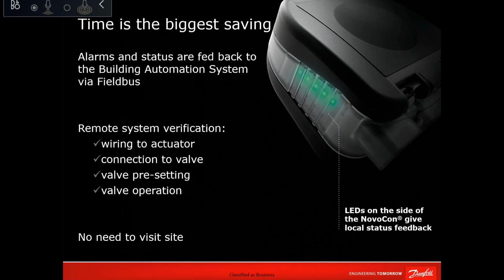Now, the maximum flow that you can have with the Novocon, up to the XL version, is 407 cubic meters per hour, or 407,000 liters per hour. This is the maximum flow. Minimum flow, as you know, is 30 liters per hour, for the smallest size. So as we said, we are covering the full valve sizes. By the end of the year, the XL will be available. So the flow rate is up to the N250, as we said, which is 407,000 liters per hour.